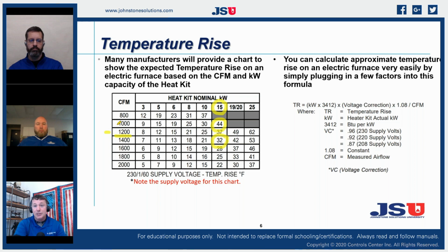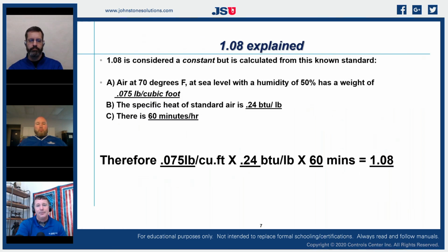Typically, it's going to be a dirty blower wheel, something that is impeding our airflow, or high static pressure, or a dirty filter, right? So looking at that chart, we can get a general idea of the operating of our duct system and the operating of our total HVAC system based on temperature rise, CFM and kW. So really good charts to be able to understand what's going on inside of there.